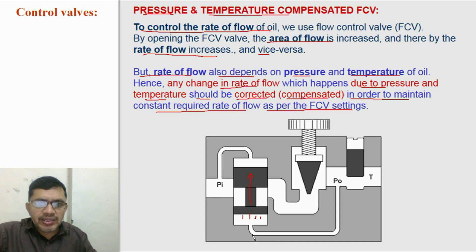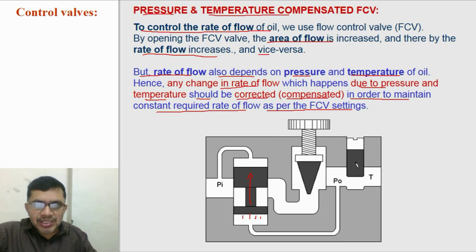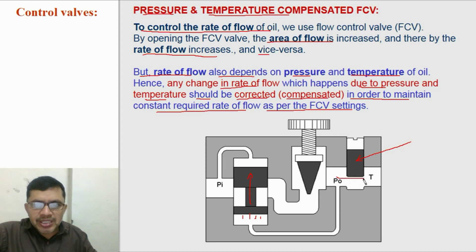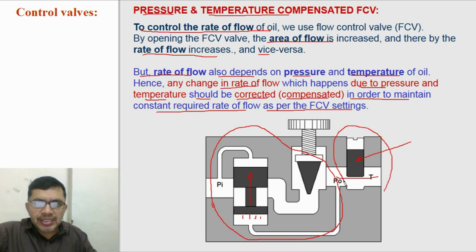And if pressure at the outlet is reduced, then naturally pressure at inlet will be more and the spool will move in the downward direction so that the flow rate will be reduced and we will get a constant rate of flow accordingly. In the same way, if temperature of oil is more, then viscosity of oil will reduce because of which flow rate will increase. To compensate this, there is a temperature sensing element with high thermal expansion. It expands and closes this passage slightly, due to which the rate of flow will reduce. So this is the pressure compensation mechanism and this is the temperature compensation mechanism.